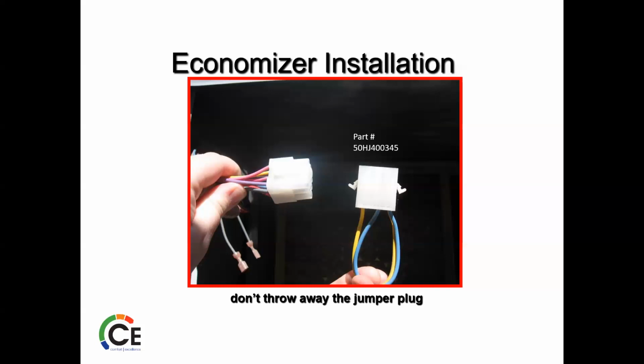So if we're testing and we want to get cooling running, then having that plug makes life easy. Otherwise, you use your wiring diagram just like we showed you before, and it'll tell you which wires to tie together, and then you can use an alligator clip or something, or a piece of wire to jump it. But if you have the opportunity to get one of those, I would definitely do it.